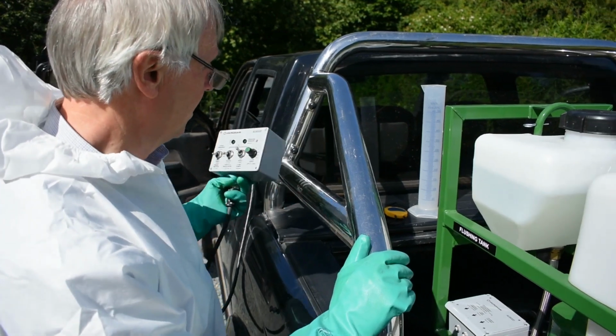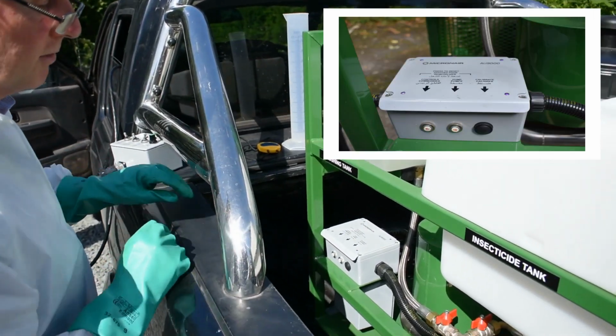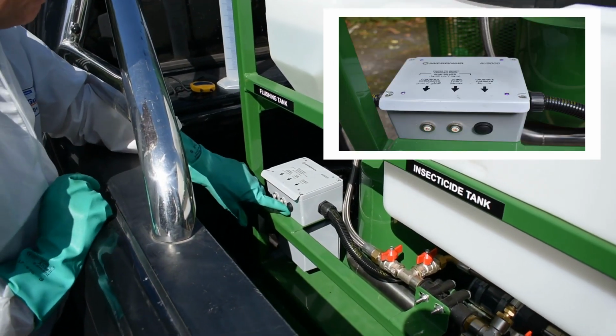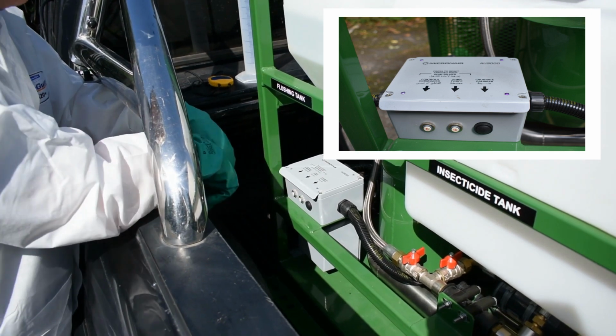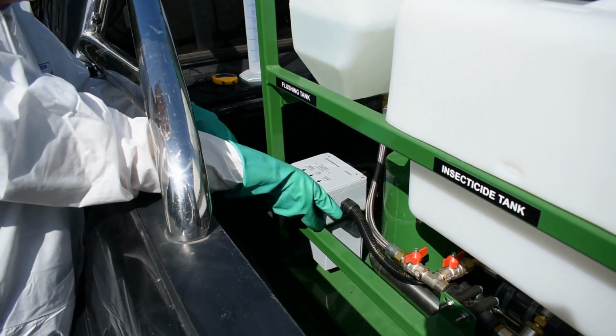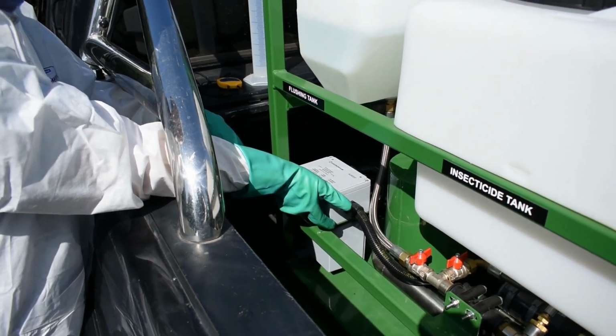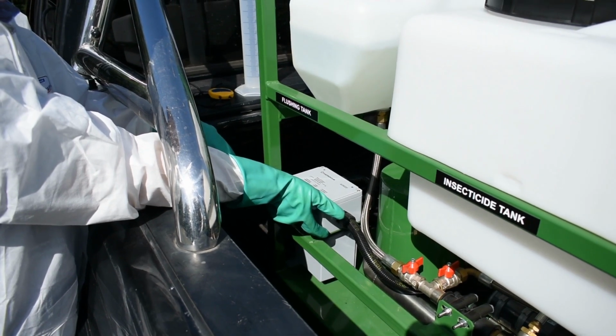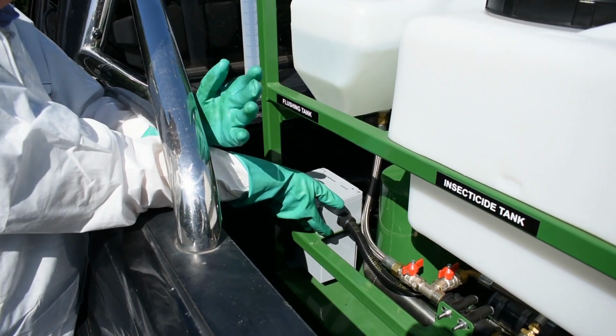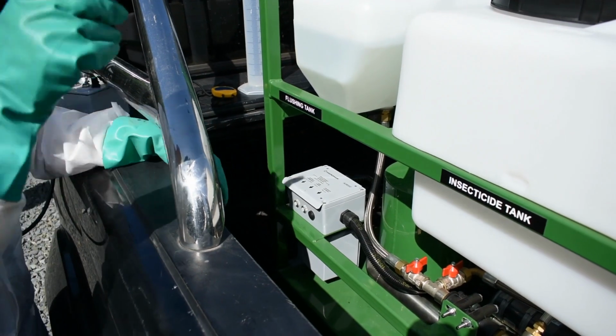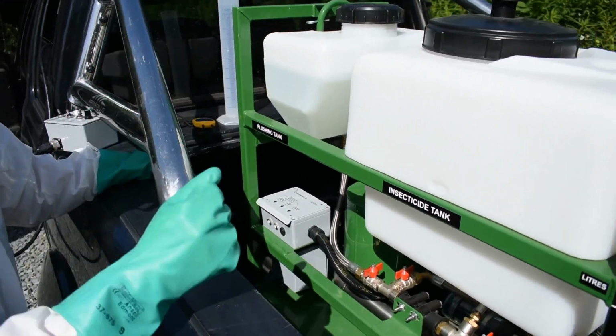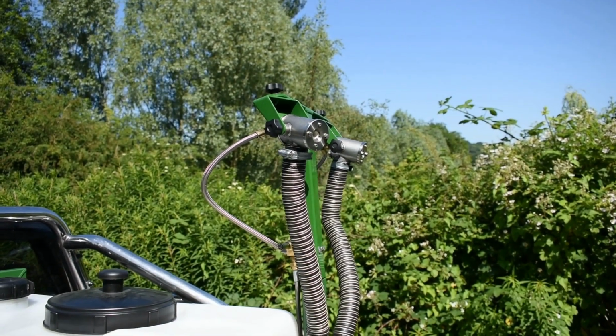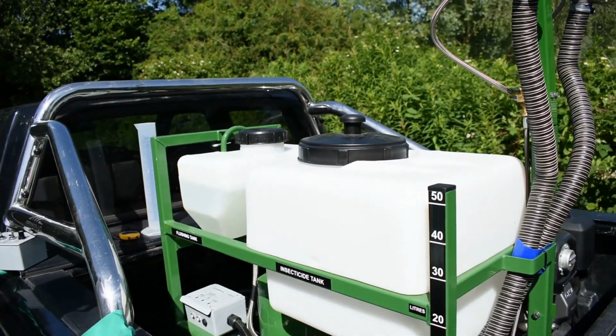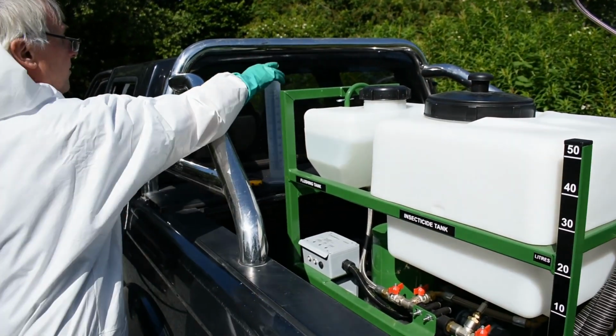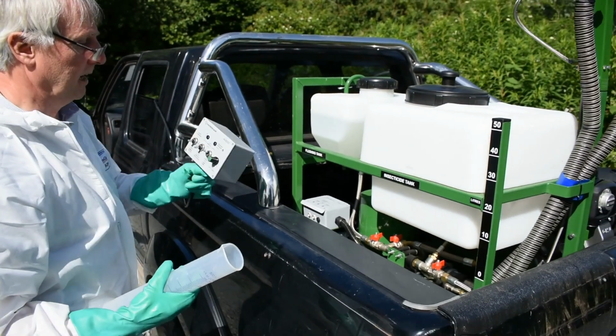So down here you have a little bypass. If you can see this button down here, the black button, which is called calibrate. If you press that button, you can hear the pump start up and the liquid will come out of the two nozzles. Now you need to do this with some buckets and pipes over the nozzles to collect the spray. Because we're using water today, we're just going to demonstrate quickly how you do the calibration.